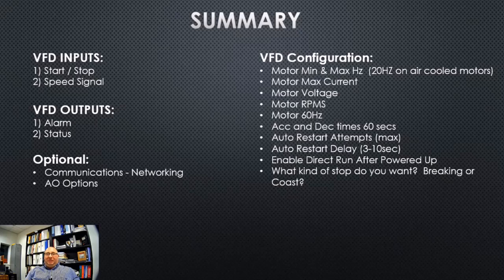In return, the drive should also send information to the equipment or to a BMS system. We want to monitor and make sure we have alarms coming out of the drive, and we also want to know that the drive is actually running. Remember what I said earlier, we could use the drive as a status point, but it's better if we use the air source or the water source as a status point, because then we'll know that we're physically moving something versus mechanically giving something power. All right, now there's options here. We could add communications for networking, and we could also use the feedback known as an analog output to have better control and monitoring of the VFD drive.